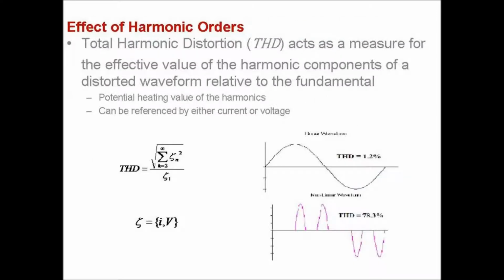And then I suppose a lot of people, when they're talking about harmonics, will reference the total harmonic distortion. This is just a measure of how bad things are. It gives you a feel for how much heating could happen because of harmonics, or how far your waveform is away from the original sinusoidal waveform. So it can be referenced in either current or voltage. So I've got the zetas in there. It's basically the sum of all of the harmonics, or all of the voltages at each frequency squared, or currents at each frequency squared, over the fundamental. So you can just sub either I or V in for zeta and everything's fine.